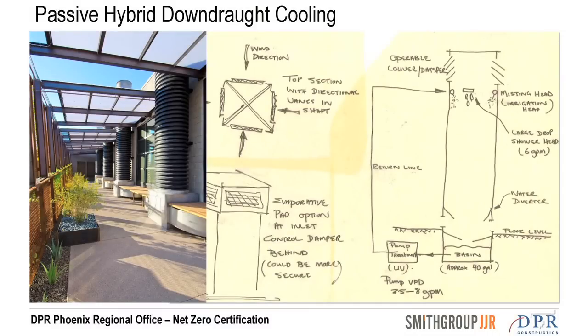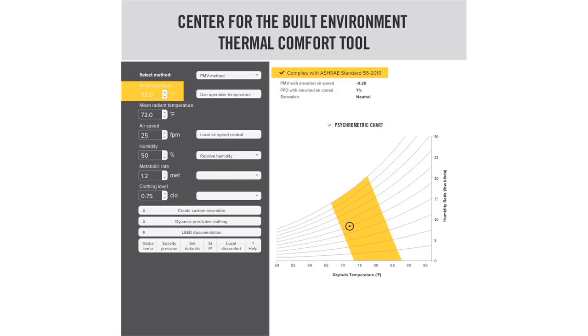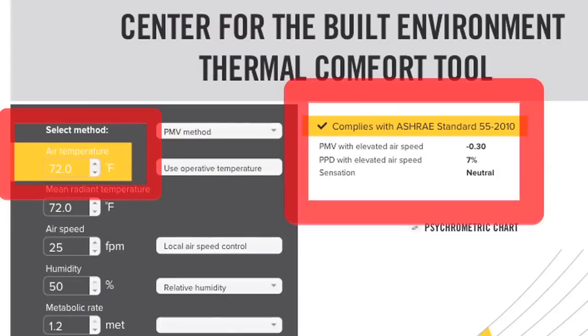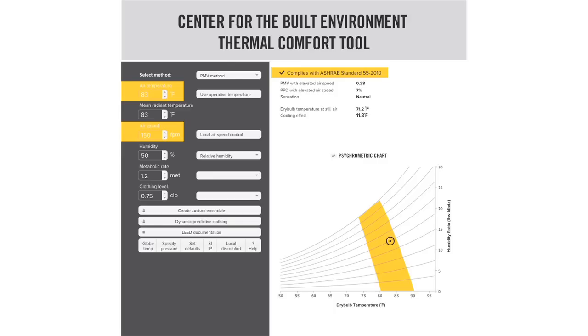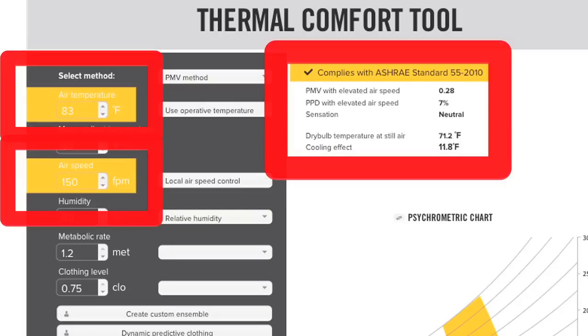That means we're using airflow to help cool people even at a higher temperature. So we operate well outside the normal of 72 plus or minus 2 degrees in our office. We operate from 68 to 83 degrees as our standard range of occupancy. That means we won't turn on any air conditioning until we cross that threshold of 83 degrees, and we don't turn on any heat until we cross the threshold of 68 degrees.